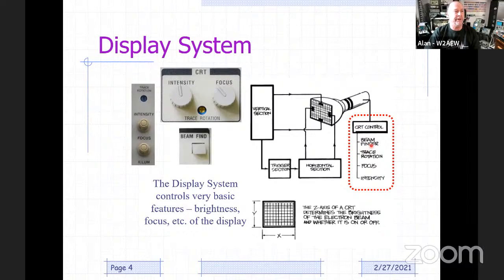And then there's one called beam finder. What the beam finder does is it collapses the deflection voltages for the horizontal and vertical down to the point where, let's say you turn your scope on, you're probing on your signal, and there's nothing on the screen. Well, why is there nothing on the screen? Is there nothing on the screen because you're not triggering right? Or is there nothing on the screen because the horizontal and vertical adjustments aren't set right, and the trace is way off the top or bottom or left or right of the screen? Hitting the beam find will collapse all those voltages so you can see where it is. Oh, it's way off to the left. I need to adjust my horizontal position to the right to get it on, something like that. But that's what the beam find is, just a momentary push button to bring the trace, if there is one, onto the screen somewhere so you can see which end it was thrown off the side of.